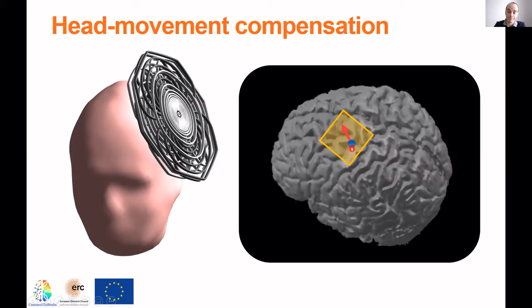is useful in practice is compensation of head movement. So typically with the conventional coil, when a patient or subject moves their head, one would need to follow the head movement by manually moving the coil in order to keep the stimulation to the site intact. But with the multi-locus transducer, one could electronically compensate for that movement. If the head moves, one can adjust the currents in real time such that the stimulated cortical site would remain intact.